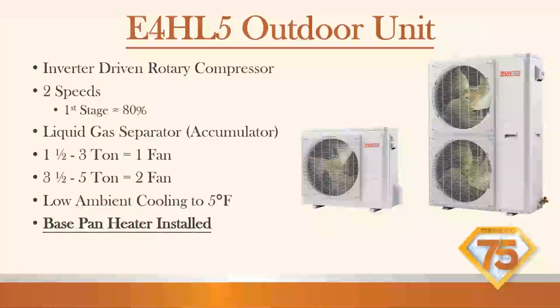All right, here's the outdoor. So we got the E4HL5 outdoor unit. This is an inverter driven rotary compressor. So when you hear inverter, it's capable of many speeds, but the way it's being communicated, it's only 2 speeds. So we got a Y1, Y2. So first stage is 80%.